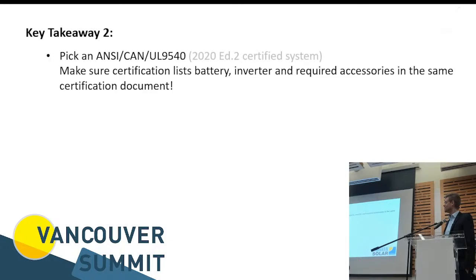The key takeaway here is, if you can, pick a system that is UL 9540 certified. Unfortunately, a lot of manufacturers have some certification to the old code, the 2016 version, where they could issue documentation for each component separately. But that is not what's accepted under the 2021 CEC code. So make sure that if you look at documents from any manufacturer, they actually have the 2020 version in addition. That's a very small detail, but it's a very big difference in getting your system through inspection or not.